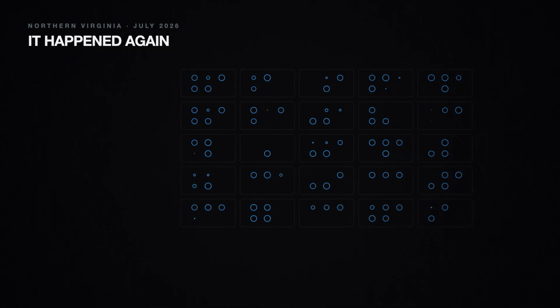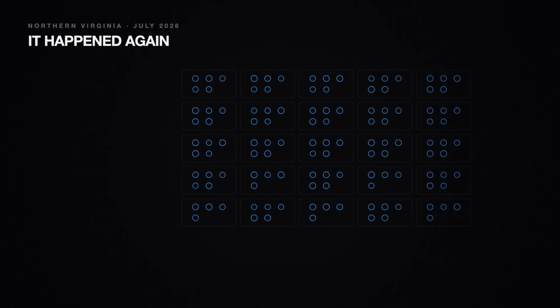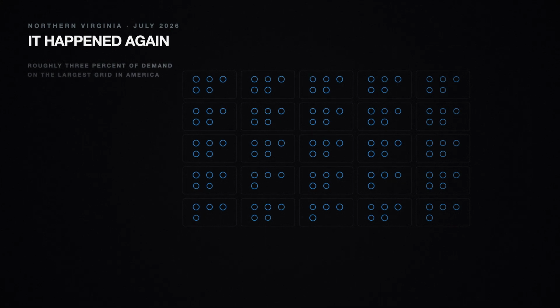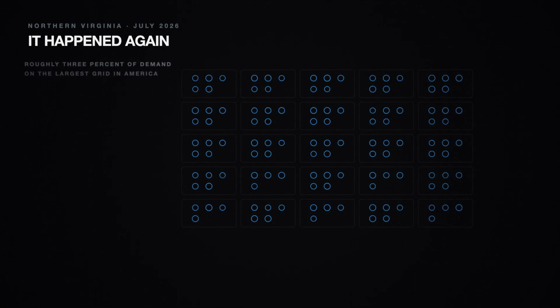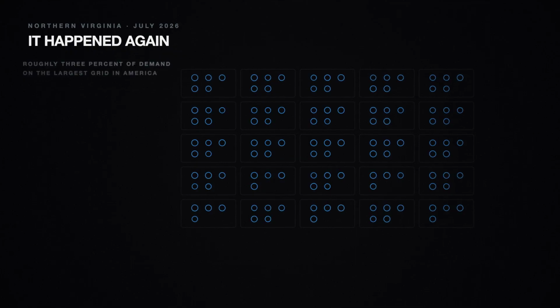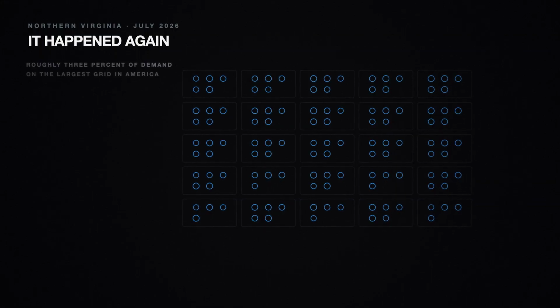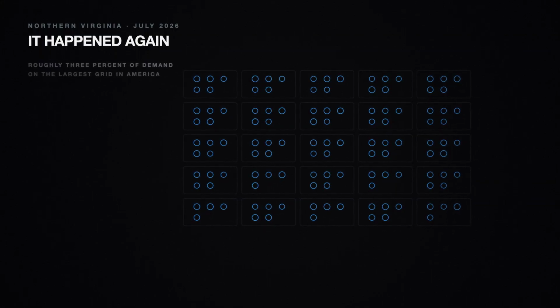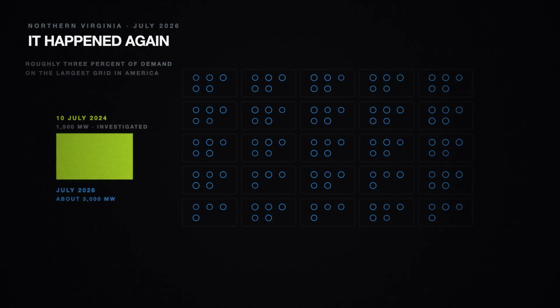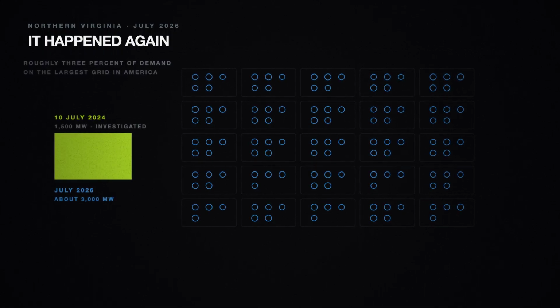One last thing, and then I will stop. In July 2026, it happened again. Same region, same kind of event. About 3 gigawatts of data center load disconnected at once, roughly 3% of demand on the largest grid in America, and the disturbance was visible on instruments from Washington to Chicago. Twice the size of the event this film opened with.